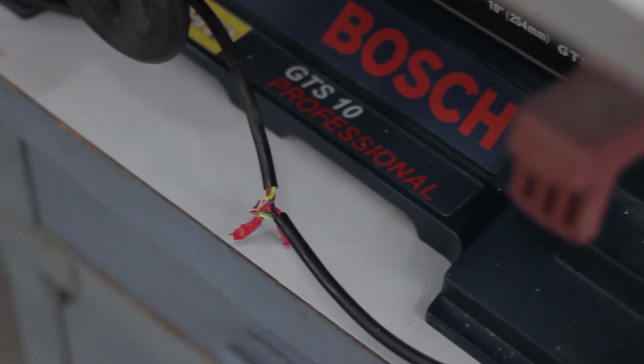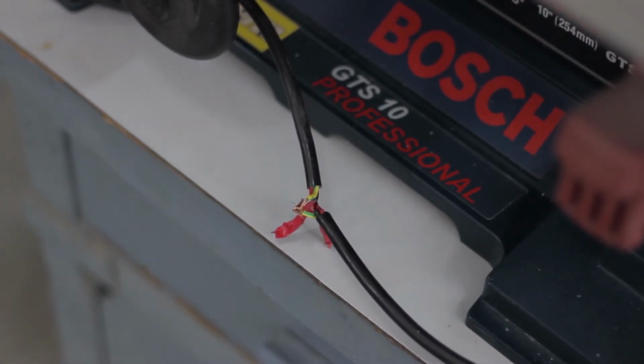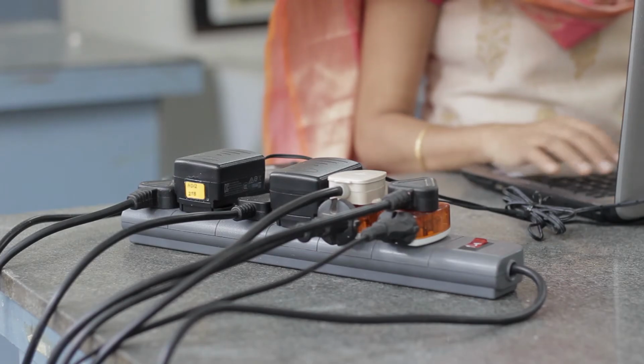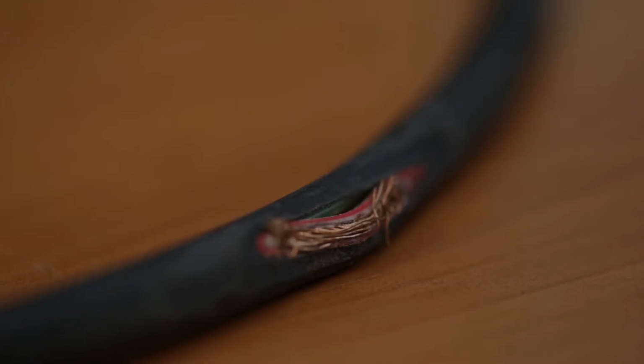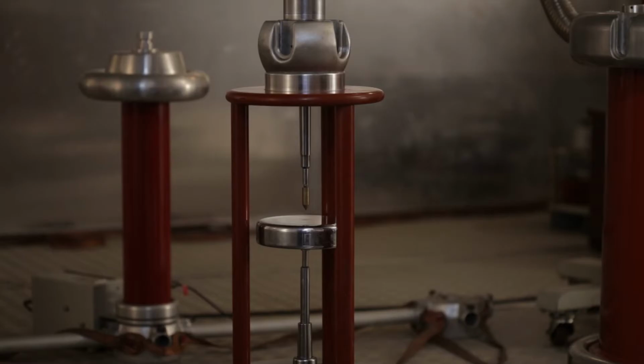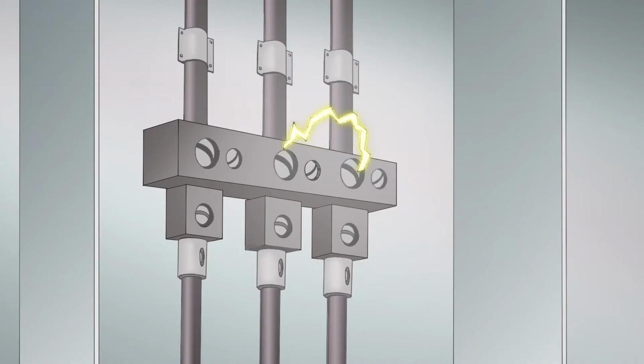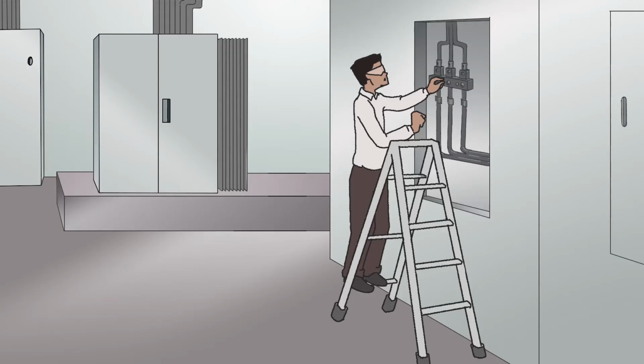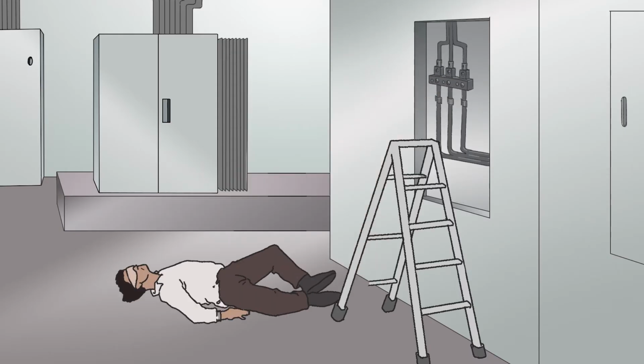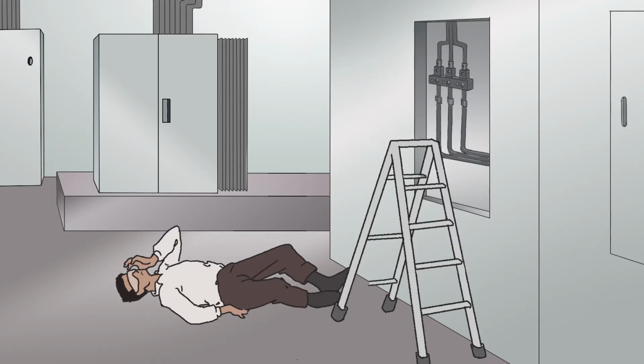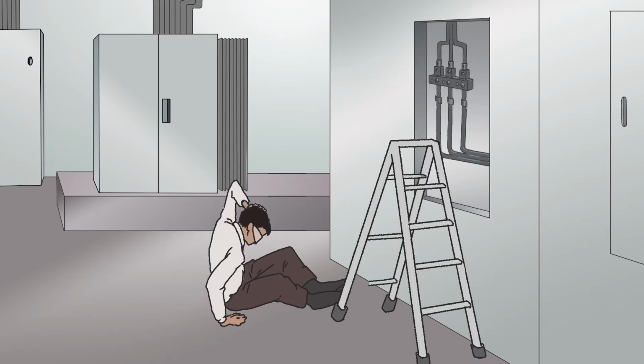Electrical fires are mainly caused by loose contact in electrical connections, overloading of electrical circuits, and deterioration of insulation. Electric arcs and sparks can ignite flammable gases and vapors in the vicinity. An arc flash is caused by the rapid release of energy due to an arcing fault between two conductors. Electric shock can cause a person to lose balance and fall from height, resulting in serious injuries. Electric shock can also cause heating of tissues, causing severe burns.